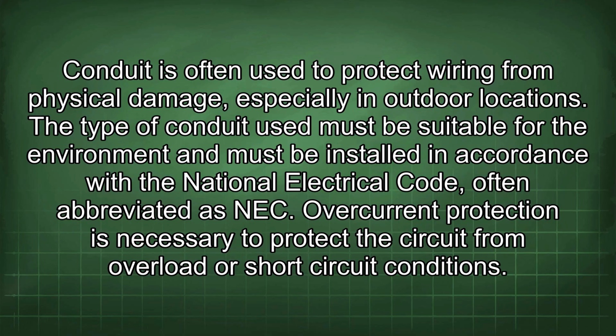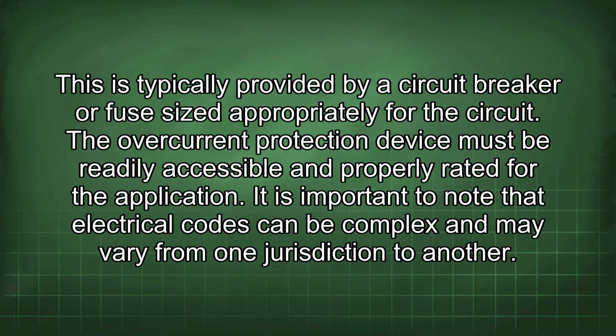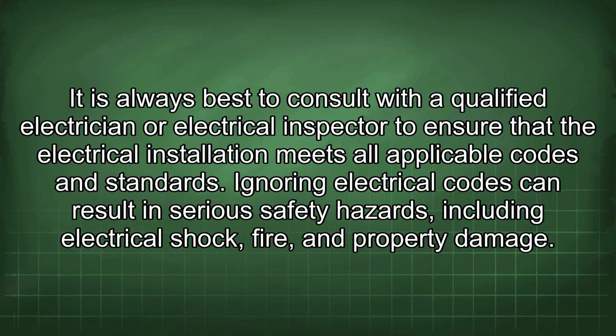Overcurrent protection is necessary to protect the circuit from overload or short-circuit conditions. This is typically provided by a circuit breaker or fuse sized appropriately for the circuit. The overcurrent protection device must be readily accessible and properly rated for the application. It is important to note that electrical codes can be complex and may vary from one jurisdiction to another. It is always best to consult with a qualified electrician or electrical inspector to ensure that the electrical installation meets all applicable codes and standards. Ignoring electrical codes can result in serious safety hazards, including electrical shock, fire, and property damage.